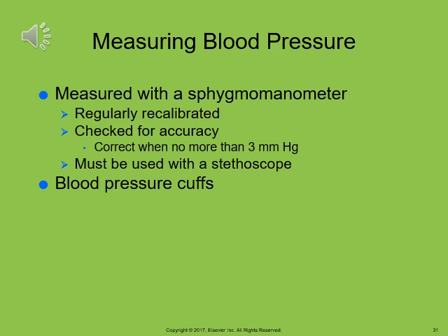The needle on the aneroid dial sphygmomanometer should rest within the small square or circle at the bottom of the dial. The dial can be calibrated by connecting it to a calibrated manometer. If you have a patient who is monitoring their pressure at home, be sure that they understand the mechanics of obtaining a reading accurately. Procedure 7.7 describes how to determine a patient's blood pressure.